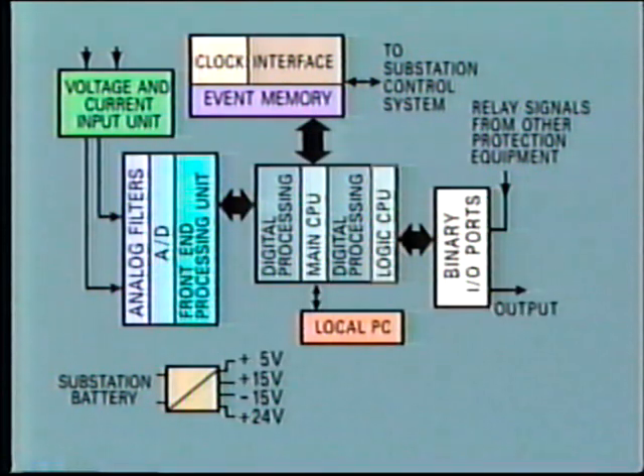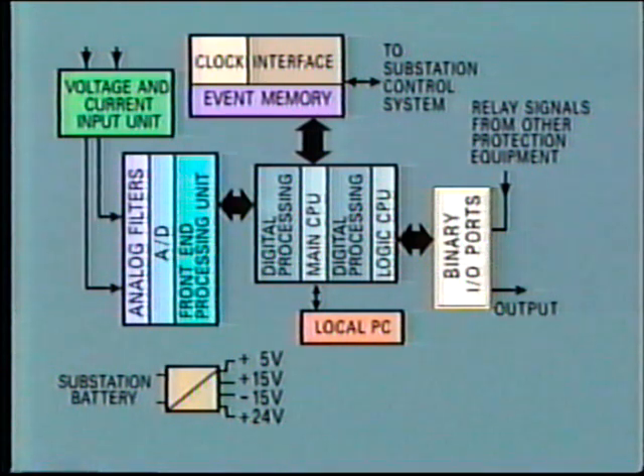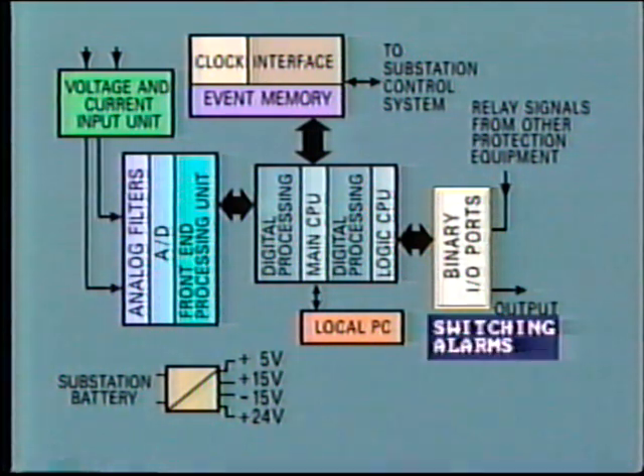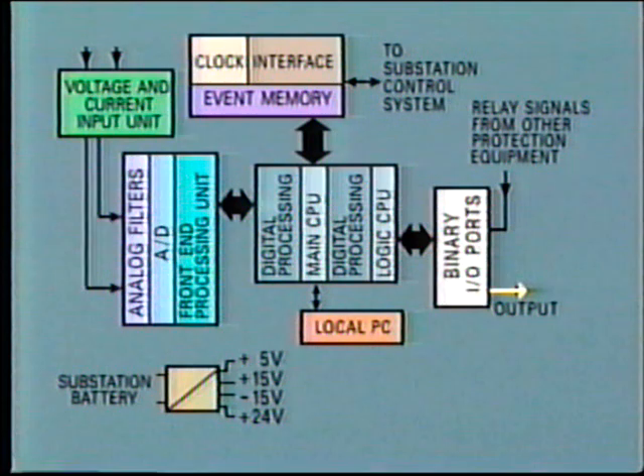The main processing unit also includes a logic processor, where the relay signals are compared with incoming relay signals from other protection equipment. For example, pilot protection carrier communication. Such relay signals from other sources are fed into the input-output module. This unit also provides the output for switching and alarm circuits. Output in digital form is also provided for use by other relays or the substation control system, for example, reclosing arrangements. These signals can also be used to operate a digital event recorder or oscillograph.